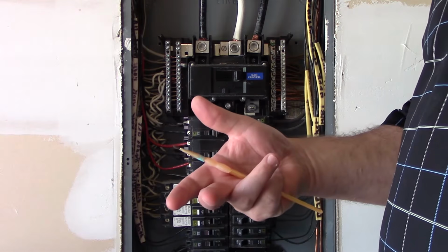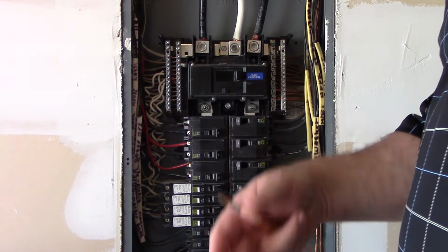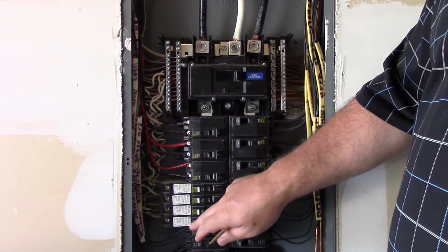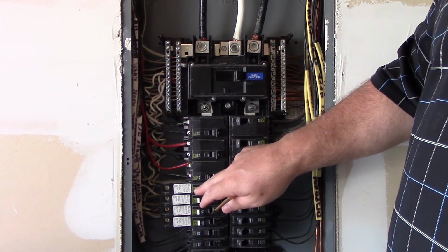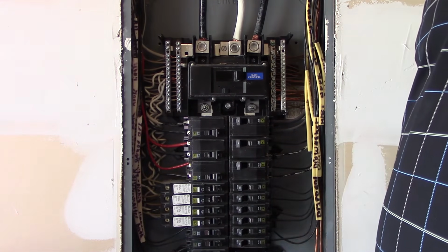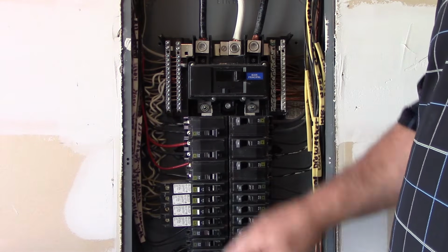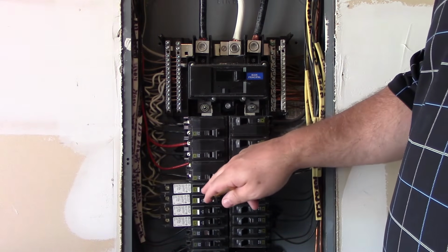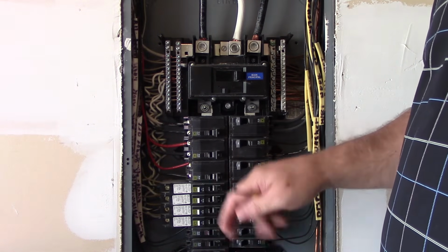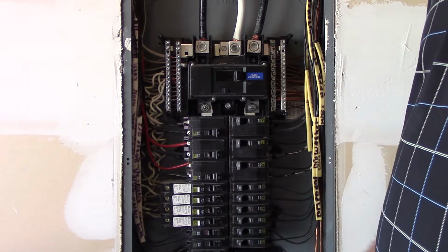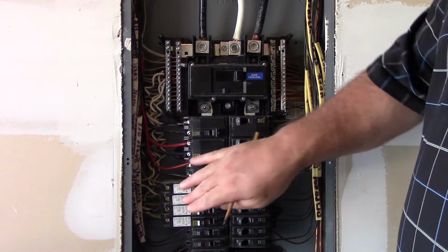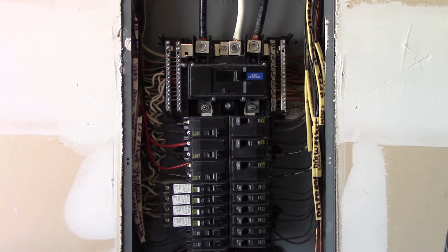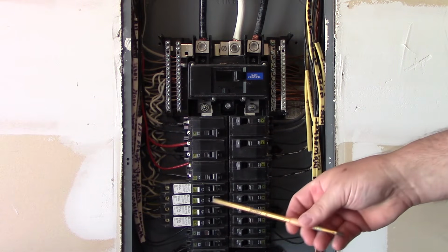You have little AFCI testers out there, but the reality is these are the buttons that I want to test it by. If I test this button right here, then I would go in and check that circuit, make sure it corresponds to the directory, make sure it actually does what it says it's going to do, and then I would reset it. So you do trip them and reset these. So I trip it all the way off and then back on, and that's what I'm going to do for these here. All right.